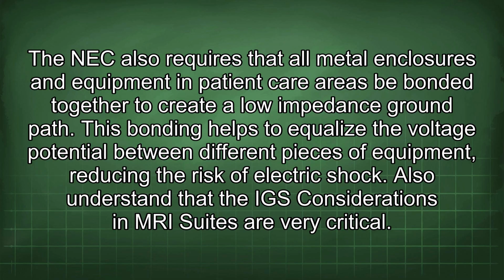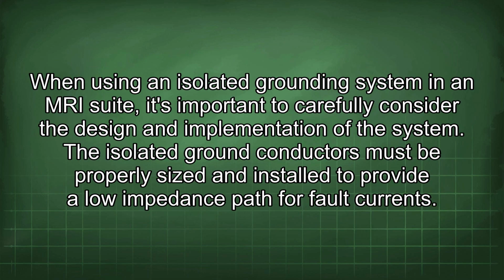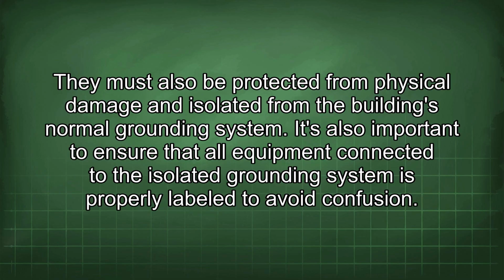The NEC also requires that all metal enclosures and equipment in patient care areas be bonded together to create a low-impedance ground path. This bonding helps to equalize the voltage potential between different pieces of equipment, reducing the risk of electric shock. Also understand that the IGS considerations in MRI suites are very critical. When using an isolated grounding system in an MRI suite, it's important to carefully consider the design and implementation of the system. The isolated ground conductors must be properly sized and installed to provide a low impedance path for fault currents. They must also be protected from physical damage and isolated from the building's normal grounding system.